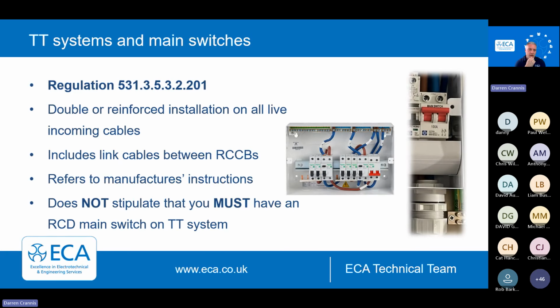Another common one as well is we spoke a lot about TT today and RCDs, and especially in domestic scenarios, that RCD main switch is required. So we have a regulation on this, and it's a UK specific one. We talk about double reinforced insulation on those live incoming cables. So those cables from the meter will be insulated and sheathed, and that meets our double reinforced protection methods. Importantly, when we install these, we keep those as short as possible, so no one can hang their coats on them or swing from them. We clip those on the way. We use a proper tail gland. They're relatively inexpensive these days, that grasps the cable. And importantly, we keep it insulated and sheathed all the way into the main switch. So we can still use that main switch, but we're making sure that any earth fault is absolutely minimal.